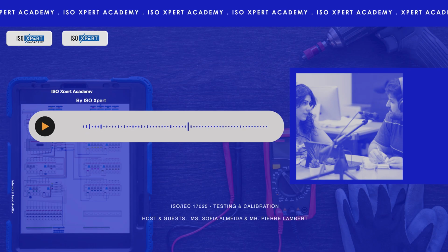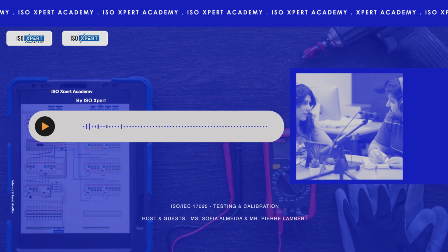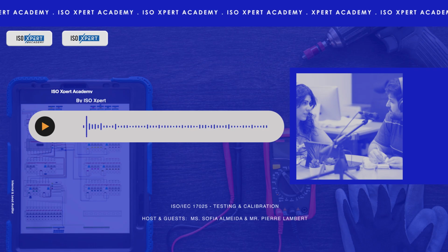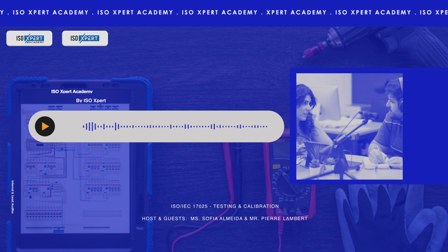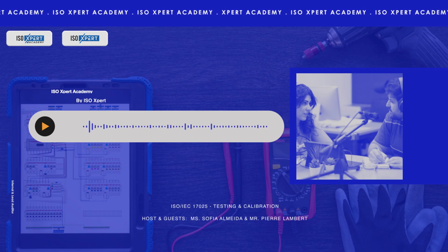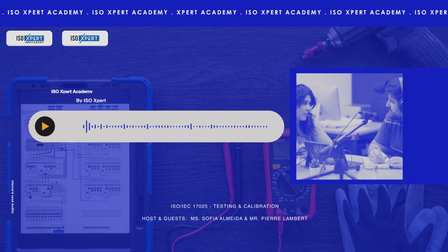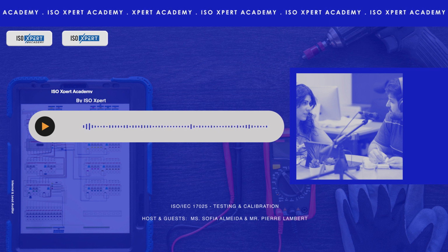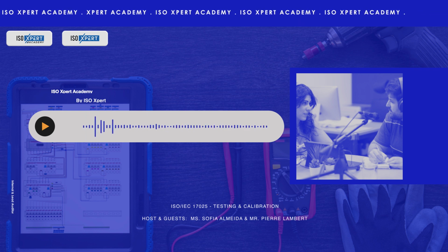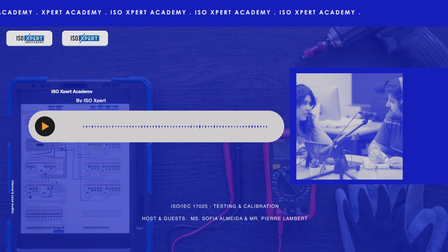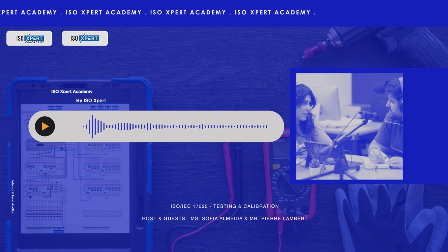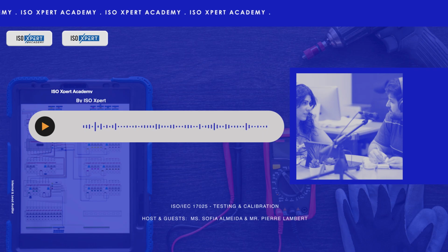It absolutely is. Then, how do you make sure the results stay valid over time? That's 7.7, ensuring validity of results. Labs can't just assume their methods always work perfectly. They need ongoing checks. Auditors look for participation in proficiency testing, PT schemes, where labs test the same blind sample and results are compared. Or interlaboratory comparisons. They also check internal quality control measures, running control samples, using reference materials, replicating tests, and if something looks off, what corrective actions are taken. It's about constant vigilance on quality.